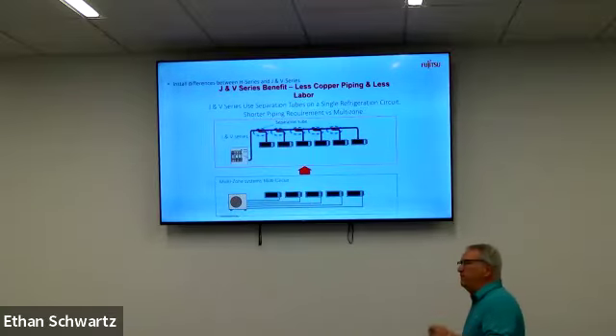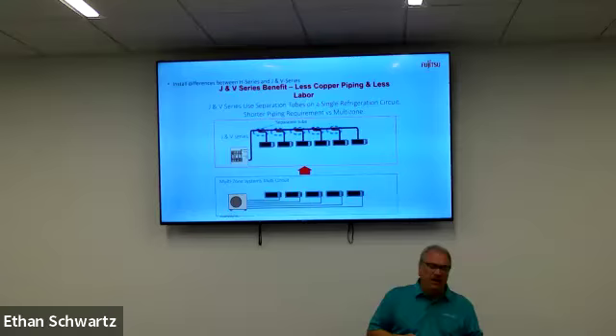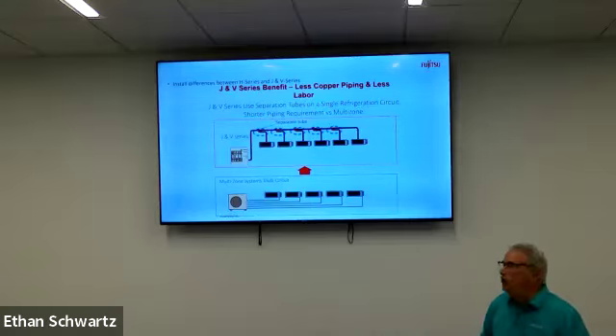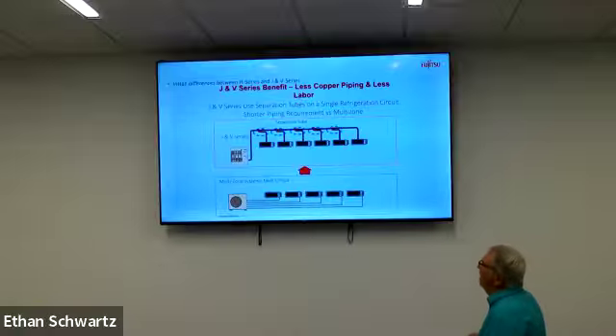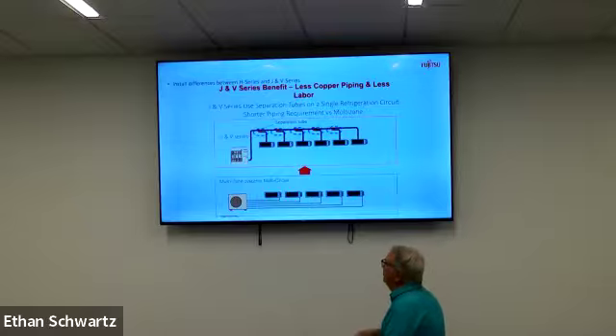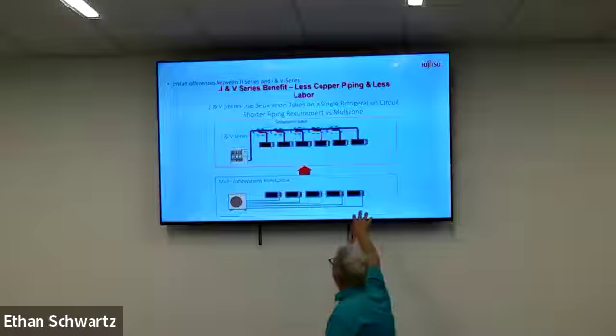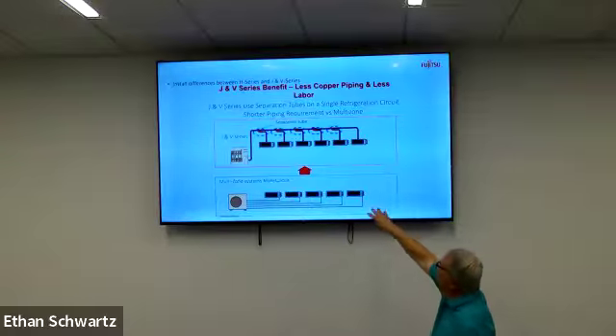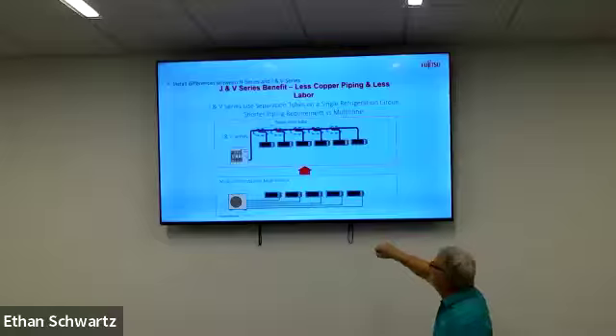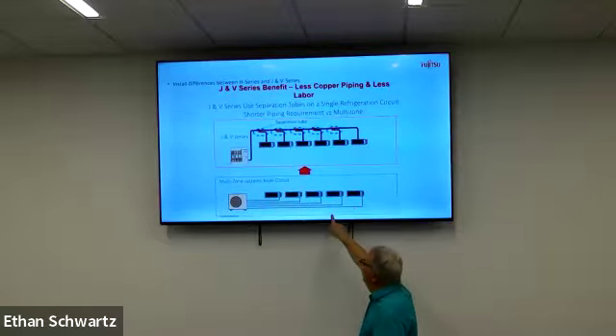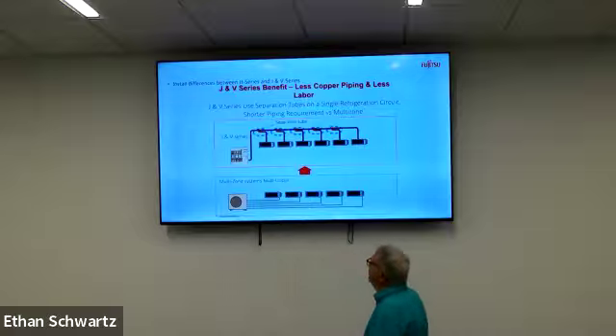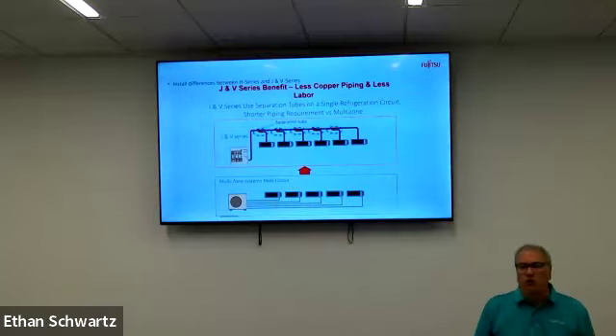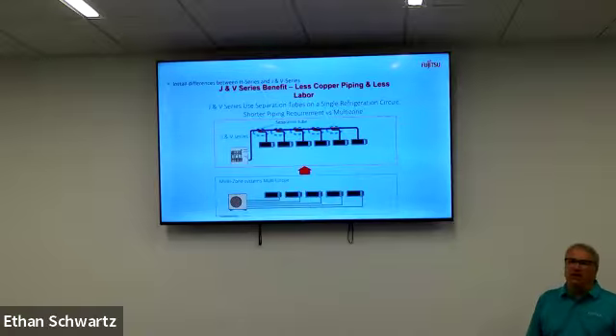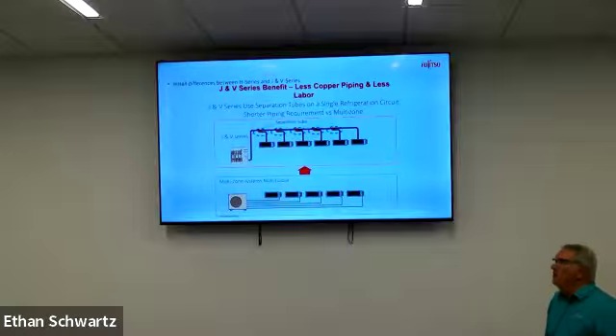What is the difference between VRF and mini splits? Many don't realize this. Many contractors don't know about this. But a VRF system does not use home run line sets. So we have an equal number of zones here, 5 and 5. Actually, that's 6 and 5. So we have a home run line set from each one of the indoor units, which is great. I mean, that's no problem, except when you get that church, that historical building, that homeowner that doesn't want to see all those line sets. They don't want to see it.